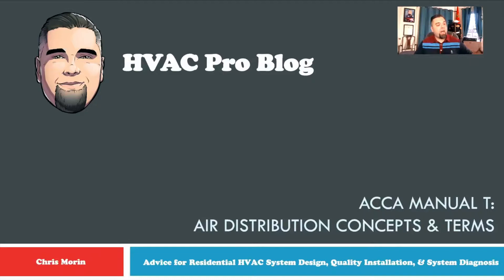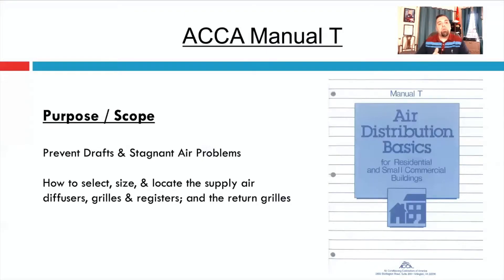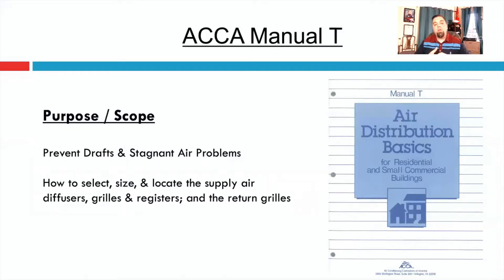A really great resource from ACCA that is very important in selecting terminal devices — Manual T. The purpose and scope of this manual is really to give you the basics so when you design your duct system you'll be able to prevent drafts and stagnant air problems that you may have if you don't select the right terminal devices. It's going to walk you through how to select, size, and locate supply air diffusers, grills, and registers, and also the return grills. Not to say you couldn't use diffusers on the return — you could, most people don't.